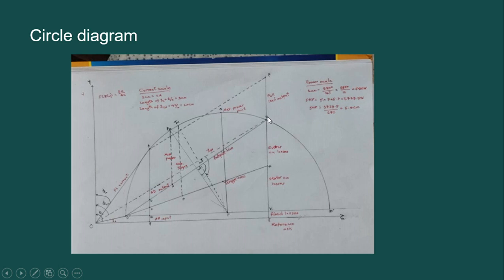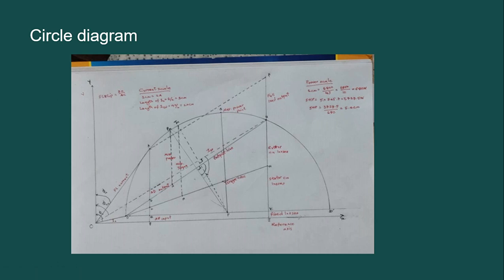Now, to represent the full load output, extend a straight vertical line from point G in the upward direction and mark it as point F. The length of G to F should be 5.4 centimeter. From point F, extend a broken line perpendicular to the ISN line and draw this broken line to a point marked as E. From point E, draw a vertical line downward to the reference axis, and also draw a line from point E to the origin. This length gives you the full load current.